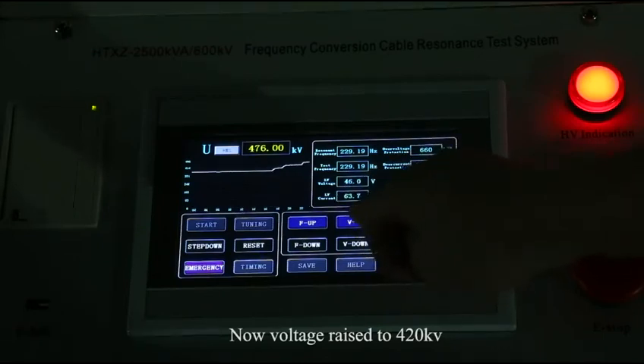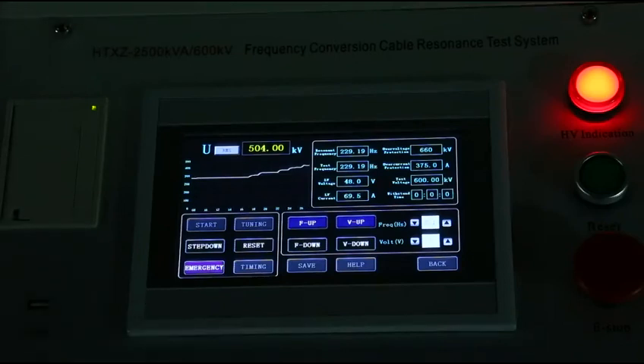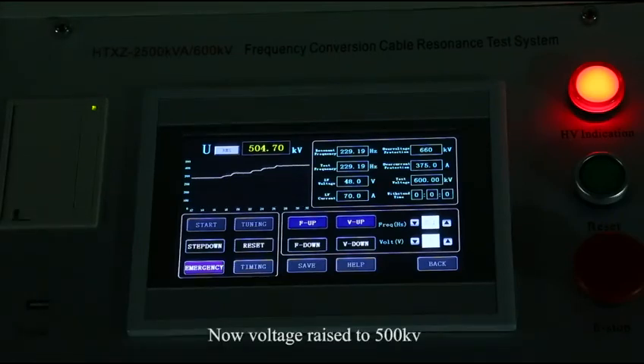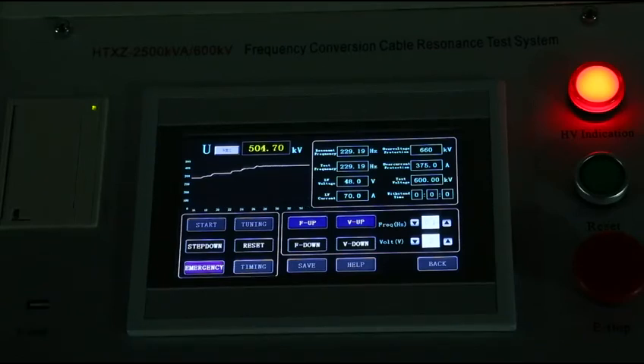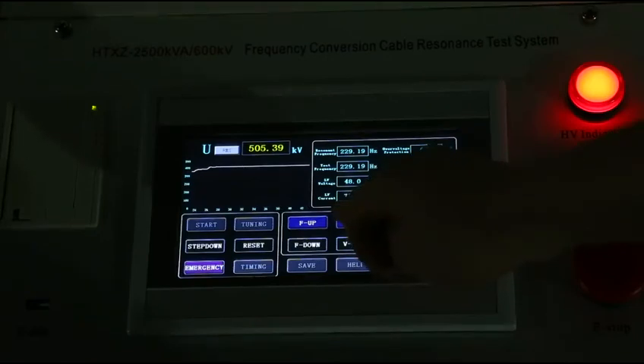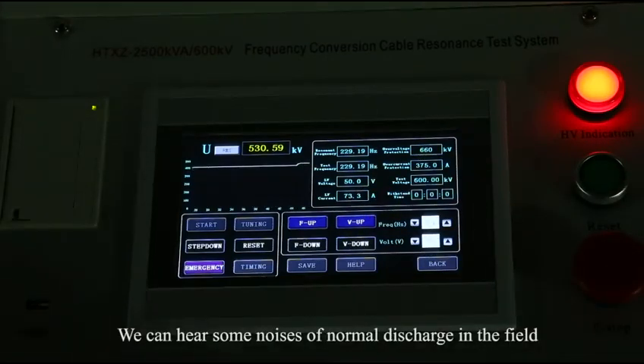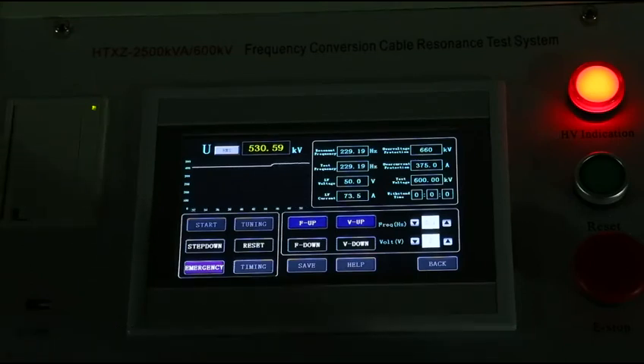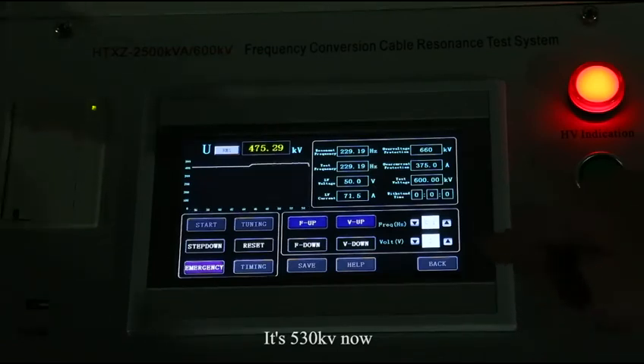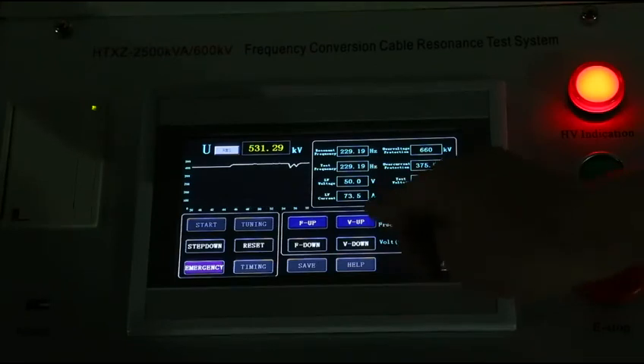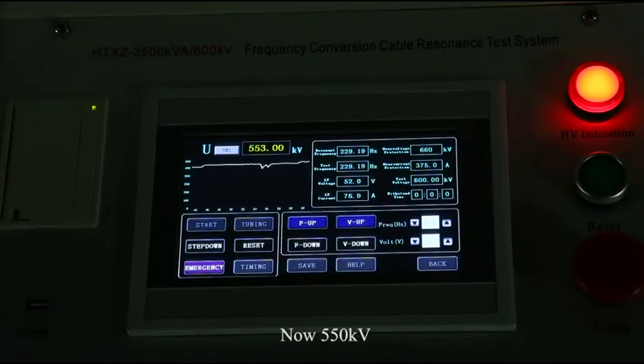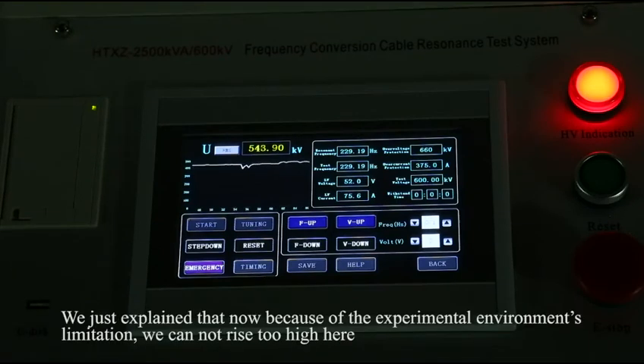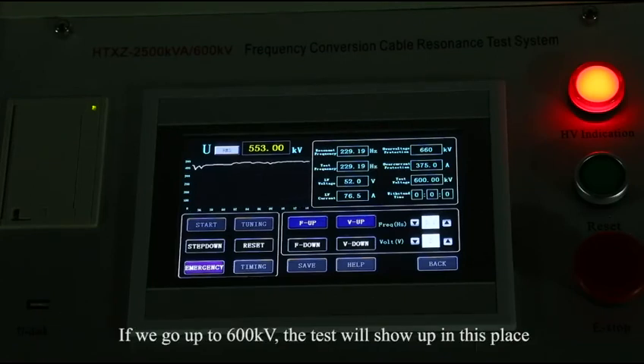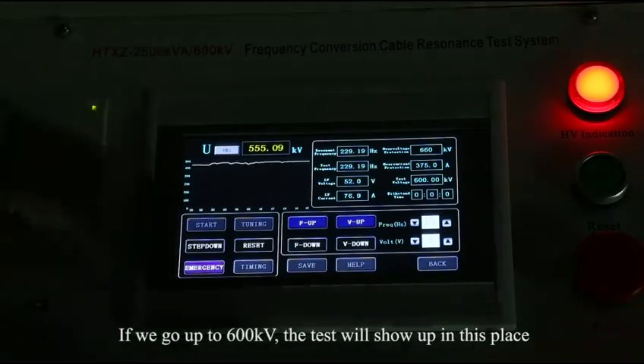Now voltage raised to 420 kV. Now voltage raised to 500 kV. We can hear some noises of normal discharge in the field. It is 530 kV now. Now 550 kV. We just explained that because of the experimental environment's limitation, we cannot raise it too high here. If we go up to 600 kV, the test will show up in this place.